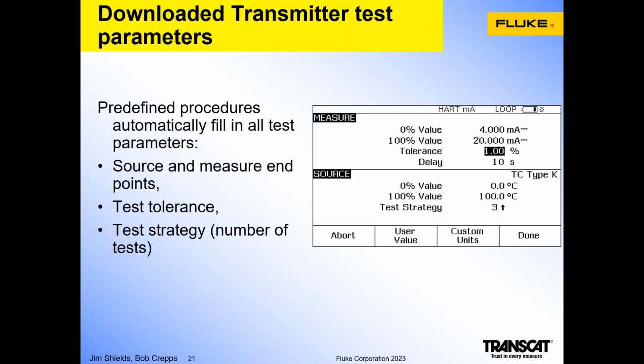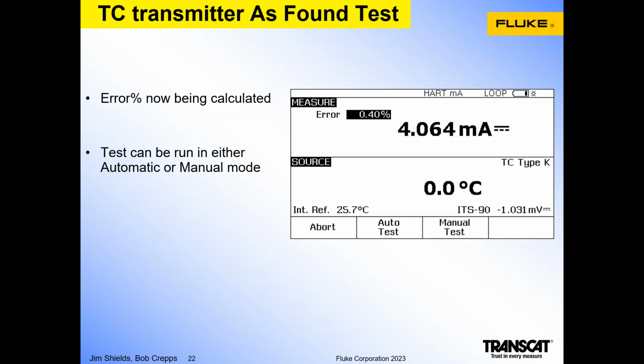The design procedures that are downloaded from the software define what's measured, the allowable deviation in the milliamp signal and the test tolerance, and the temperature value that the calibrator is going to source, and then the test strategy, which is a number of calibration test points that are being evaluated. Once the review of the procedure is complete, you'll notice here in this intermediate mode, the calibrator is ready to go out and perform a calibration.